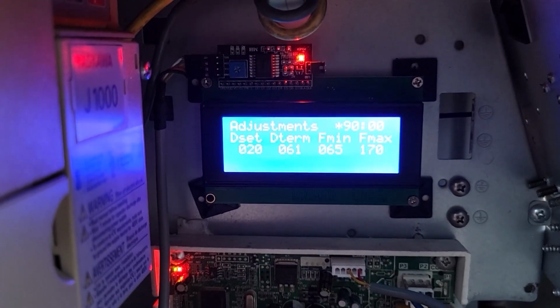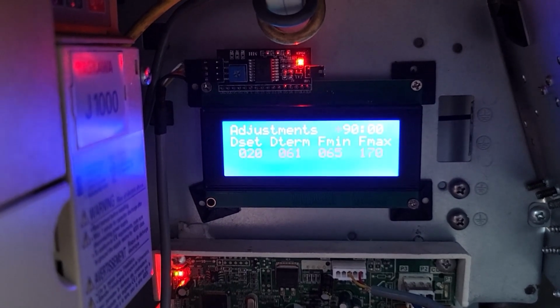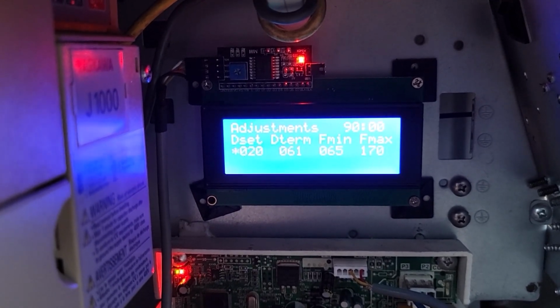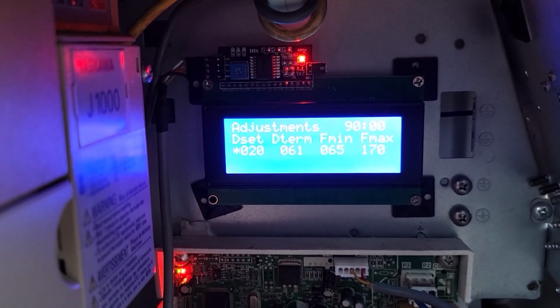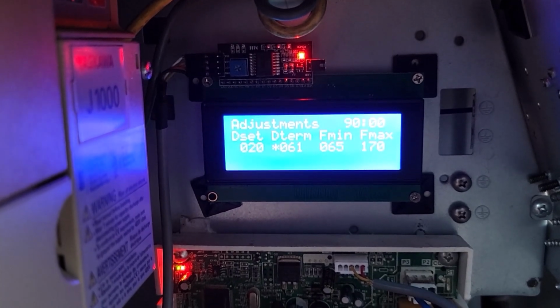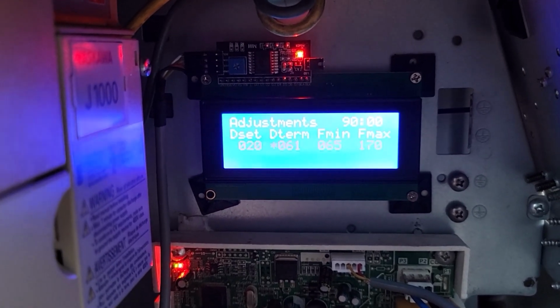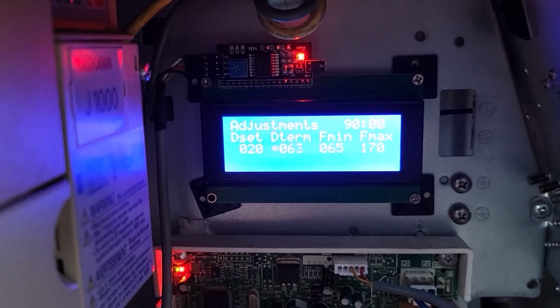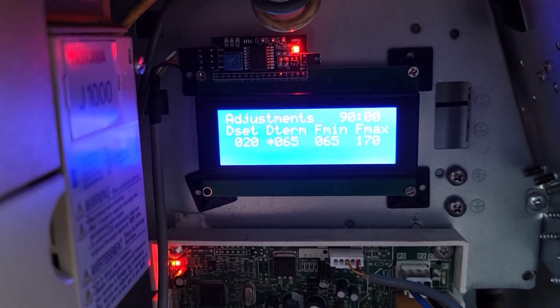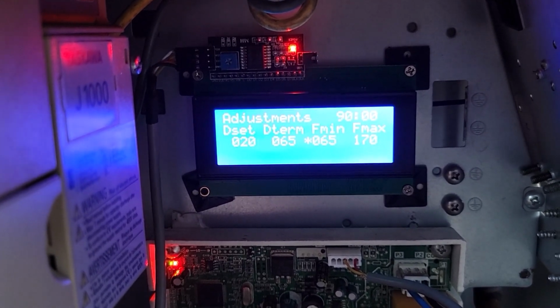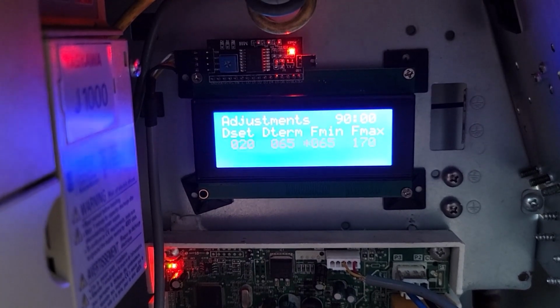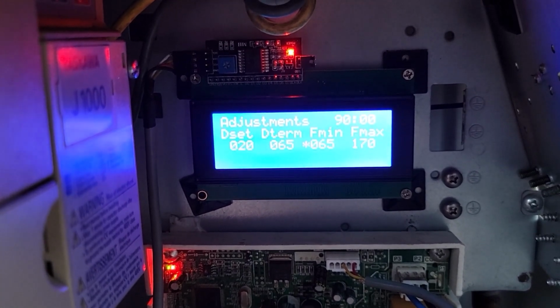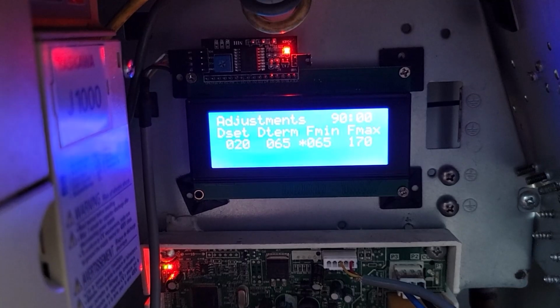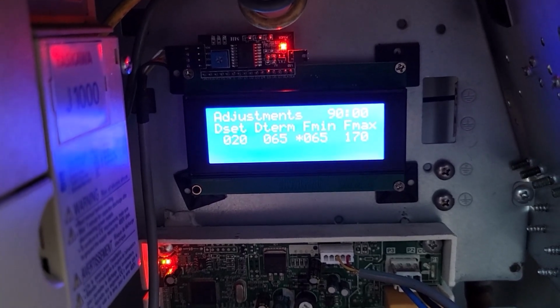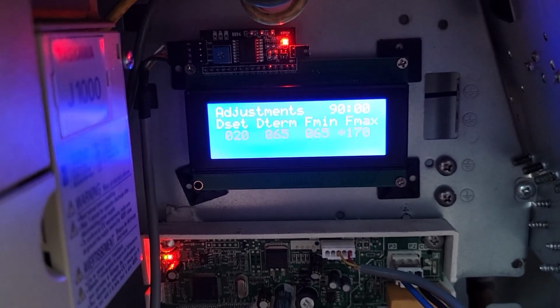I could change the interval for my defrost — 90 minutes default. Change my defrost set point — ooh, I thought I had that pretty low — defrost terminating point, so I could say it has to be, you know, 65 degrees before it terminates. My frequency minimum, this is my duty cycle, the min and max for the output for the fan. So it's 65 and then 170 right now.